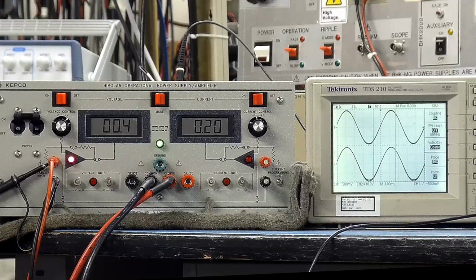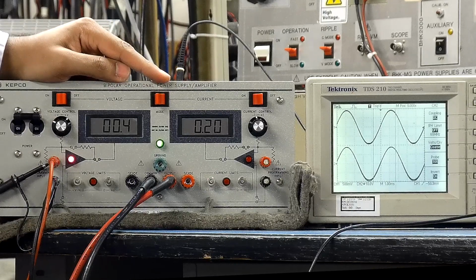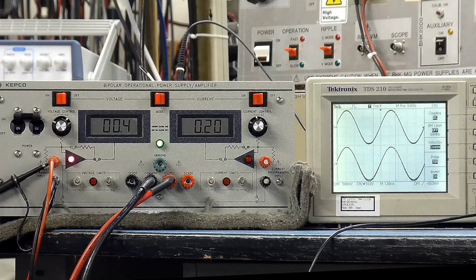To show that BOPs have truly smooth zero crossings, here we have the BOP acting as an amp. It's currently set to voltage mode with voltage control disabled, and a function generator inputting a sine wave into the voltage programming input. Any signal sent to the programming input will be reflected at the output. The input signal can be seen at the top, while the BOP output can be seen on the bottom. The BOP's displays do not appear to show the waveform. This is because the waveform being used is simply too fast for the display.